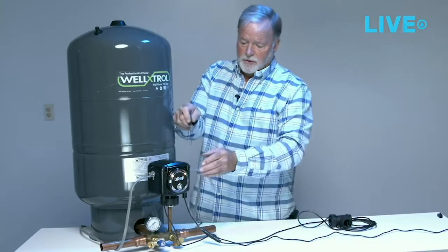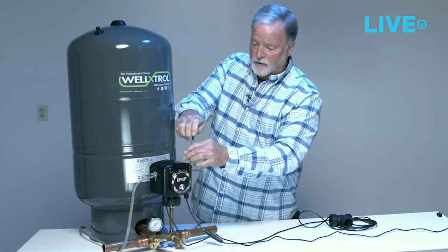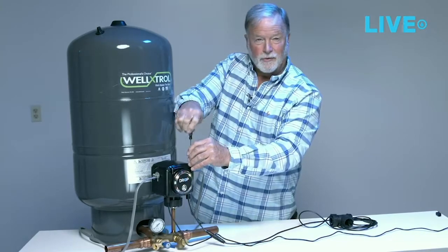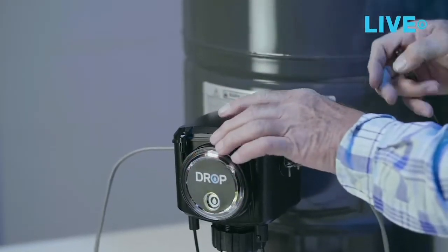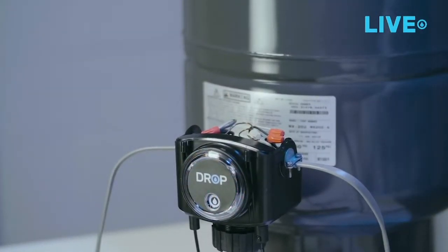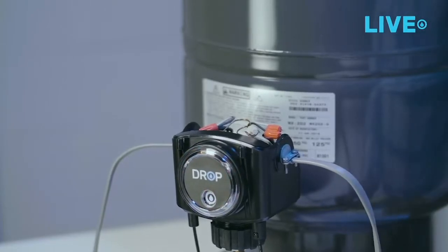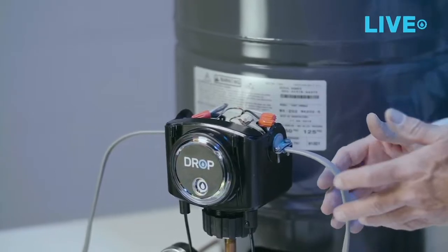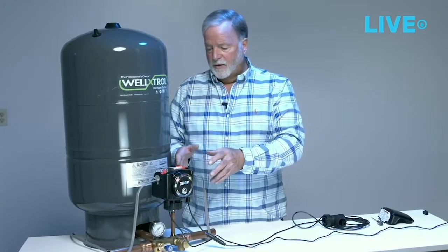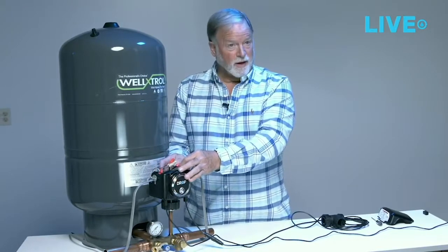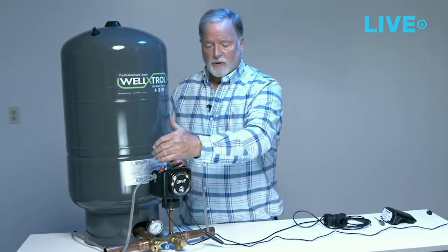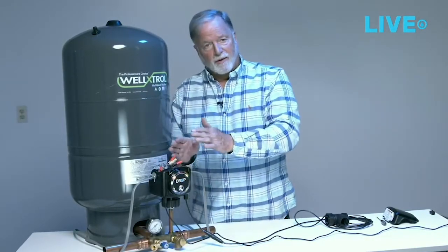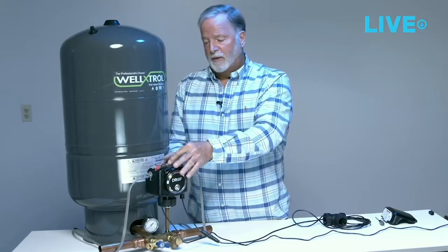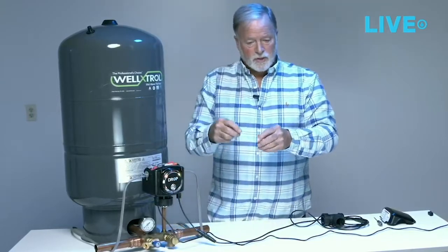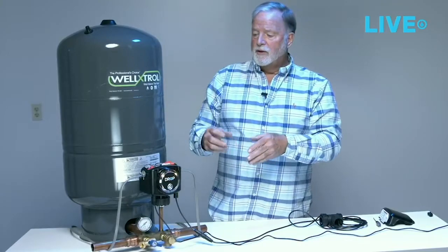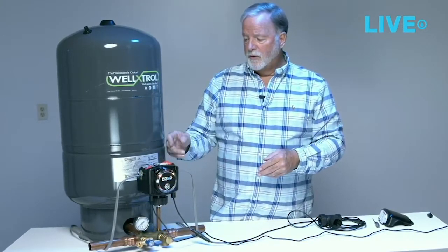The other thing then, when you raise the hood on this little guy, we've used wire tails for the connectors instead of small terminal blocks. And anybody that's ever put something like this in realizes the benefit of that. You may have a wire gauge going to your motor that's a heavier wire gauge than the terminal blocks would be made for. And in this case, you can just merely use a twist lock to connect it up. So if you had a big offset and you had to run an 8-gauge wire, for example, you could bring it in here and make it up under the hood and have plenty of room to work with. If you just had one of the typical switches with mounting screws in it, or load screws and line screws, then you're really restricted at how you can make those connections up. So we think that's a big feature.